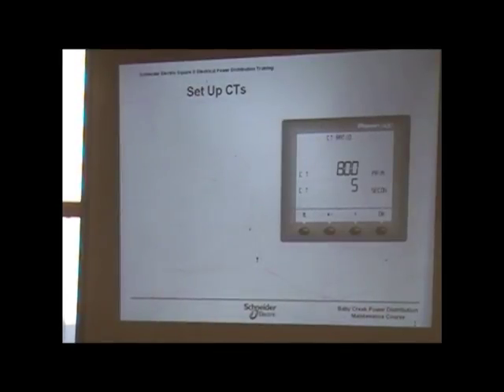I deliberately did this one because the CTs, if ever you have to replace them, that would be the main thing you would have to set up. If ever you have to replace the body or the meter, one of the things you have to set up is the CTs. Otherwise, you won't be able to read any power out. And if you ever see zeros, always go in here. Or if you don't have an amperage reading, the first thing you want to do is check to see if the CT has been set up. Because if the CTs haven't been set up, it's going to read 0 amps, and you think that it's dead.